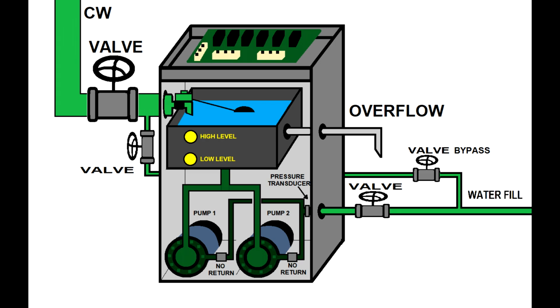Now, what does this pressurization unit have inside? On the top there is a printed circuit board, and if you look below, it is a water tank, and under the water tank you have two pumps. Those pumps are controlled by the printed circuit board, which has software that allows you to use your own set points, the pressure you want to charge the system to, and the alarms that monitor the pressure in the system.